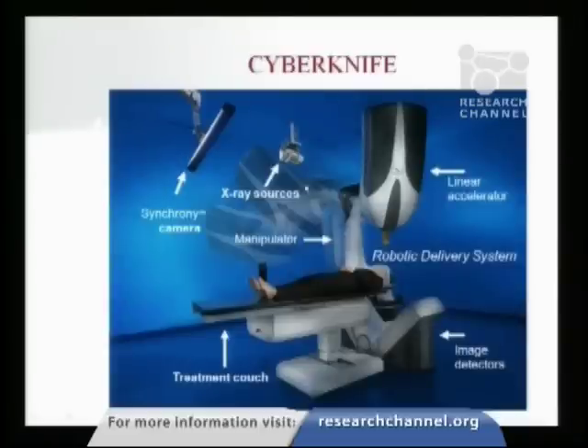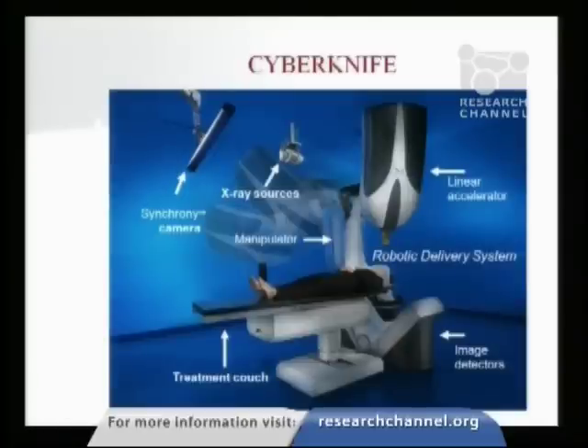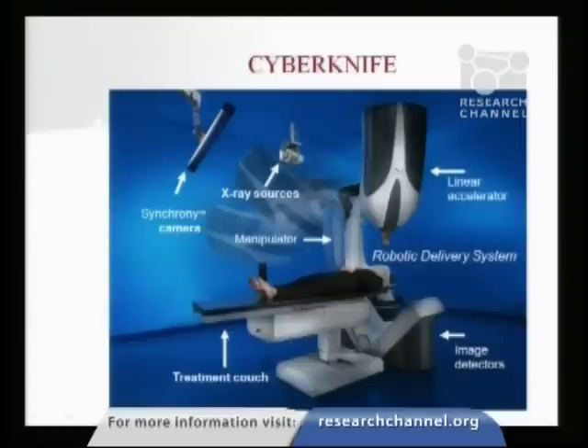During the course of treatment, these x-ray devices shoot pictures of the body part, and the amorphous silicon detector amplifies that image — a process repeated throughout the treatment. That information is fed very quickly and compared to a digital image prepared during the treatment planning process. If there's any distortion, movement, or displacement between the actual image and the digital image, those corrections are made very quickly by the robot or the couch to maintain that one millimeter degree of accuracy.